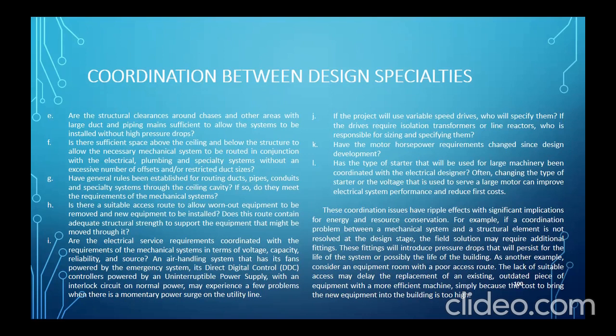This fitting will introduce pressure drop that will persist for the life of the system or possibly the life of the building. As another example, consider an equipment room with a poor access route. The lack of suitable access may delay the replacement of an existing outdated piece of equipment with a more efficient machine, simply because the cost to bring the new equipment into the building is too high.